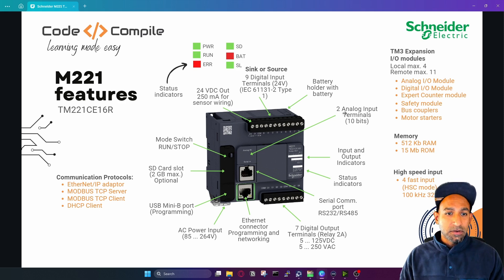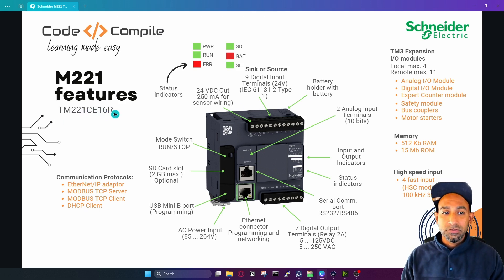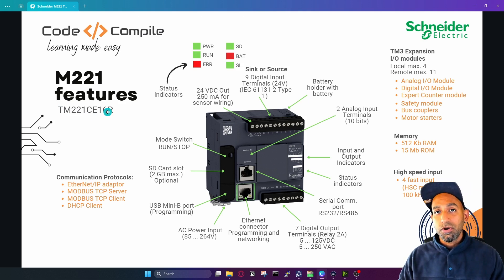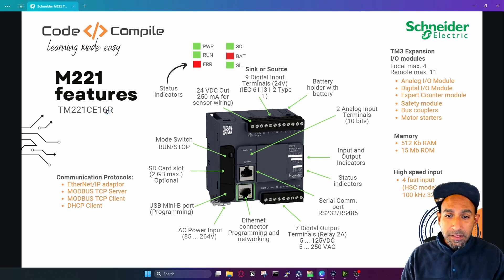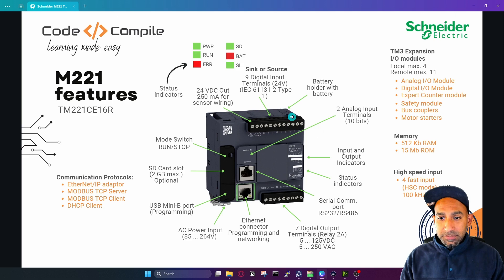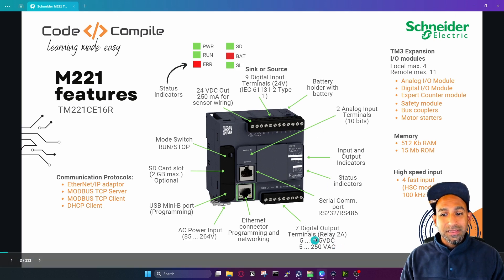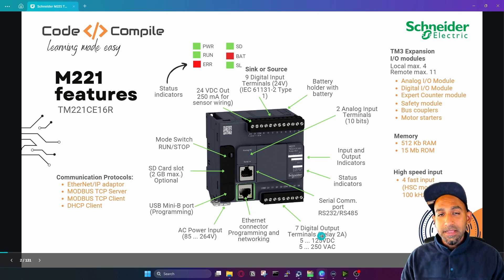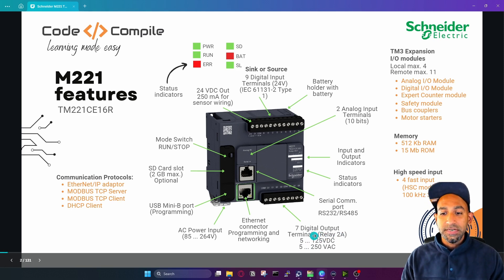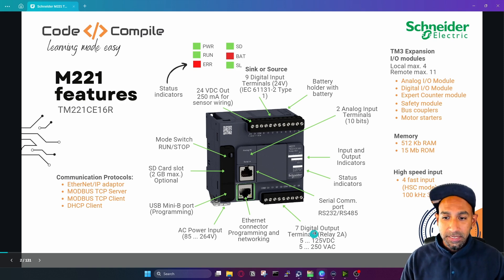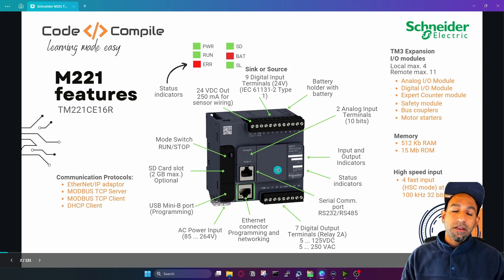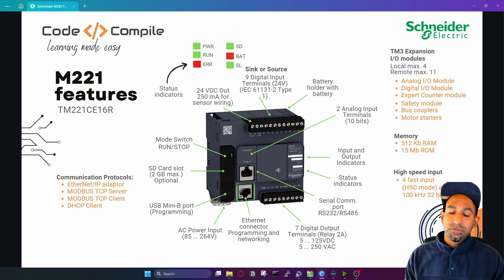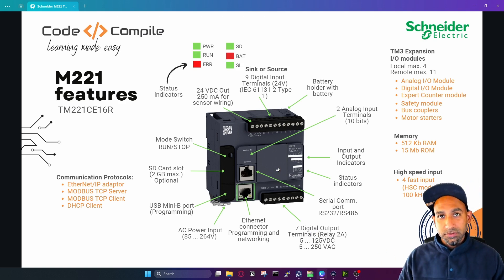The model number of this PLC is TM221CE16R. I'm going to show you how to use that in the software as well. For the outputs, we have seven digital output terminals with a relay type output of two amperes. These are the voltage ratings you can connect to these outputs. This PLC does not have analog outputs, but if you want analog outputs, you can connect an extra module next to it.